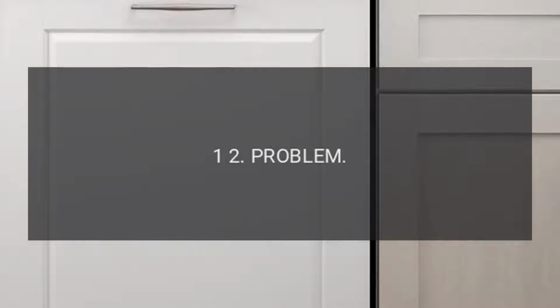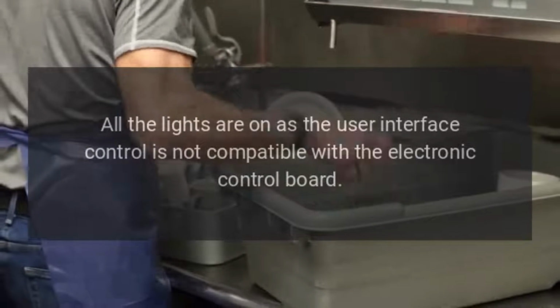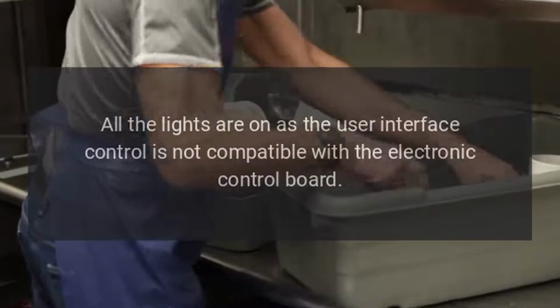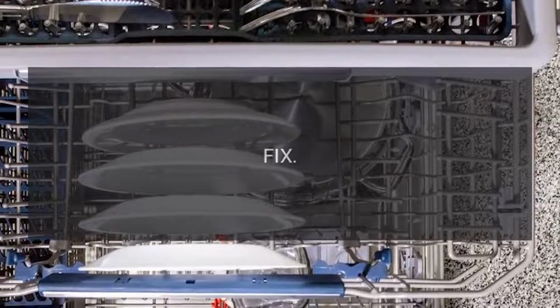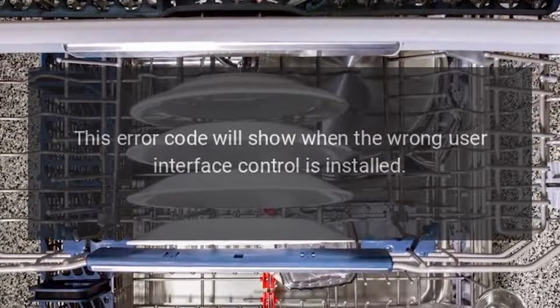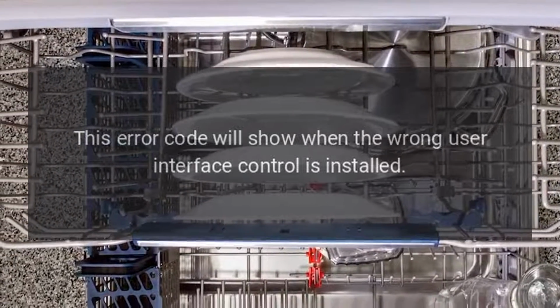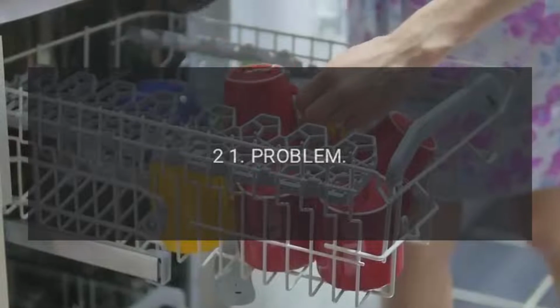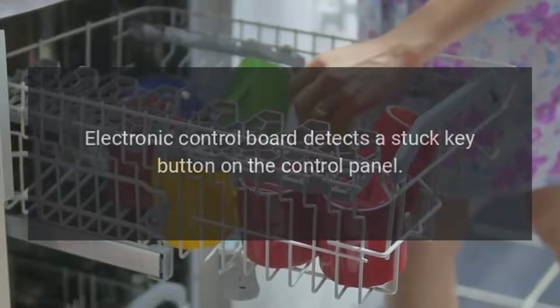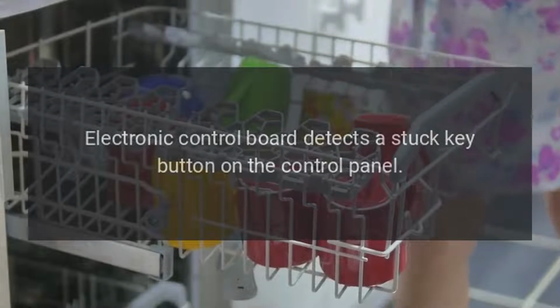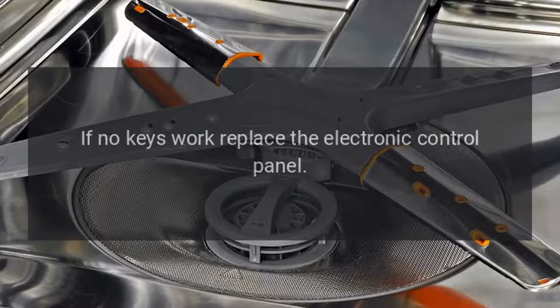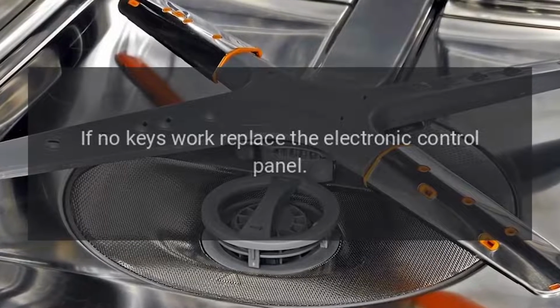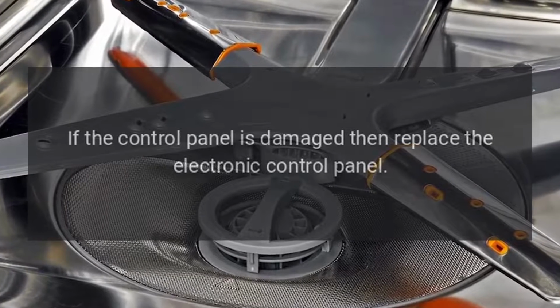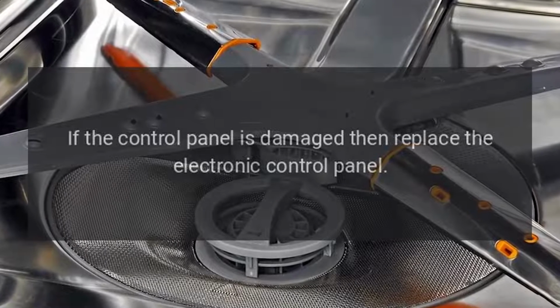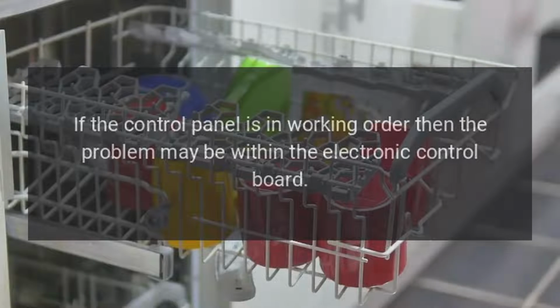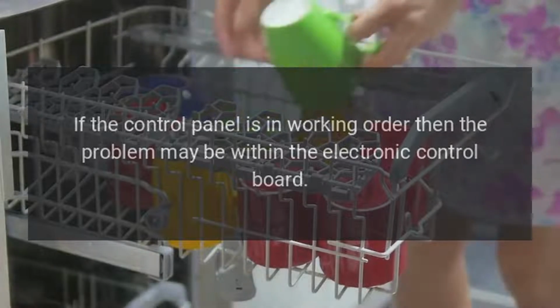Code 12. Problem. All the lights are on as the user interface control is not compatible with the electronic control board. Fix. This error code will show when the wrong user interface control is installed. Code 21. Problem. Electronic control board detects a stuck key button on the control panel. Fix. If no keys work, replace the electronic control panel. If the control panel is damaged, then replace the electronic control panel. If the control panel is in working order, then the problem may be within the electronic control board.